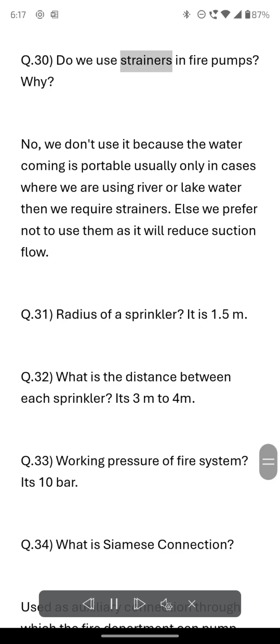Q.30 Do we use strainers in fire pumps? Why? No, we don't use them because the water coming is potable. Usually only in cases where we are using river or lake water, then we require strainers. Else we prefer not to use them as it will reduce suction flow. Q.31 Radius of a sprinkler. It is 1.5 m. Q.32 What is the distance between each sprinkler? It's 3 meters to 4 m.